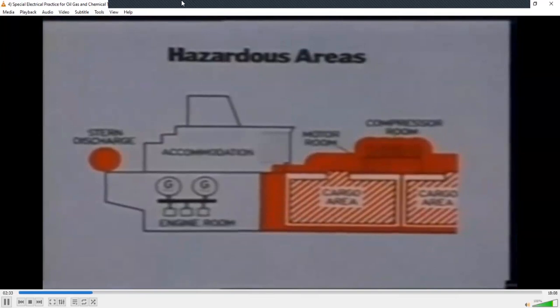The red shaded areas on this drawing show the hazardous areas relating to the electrical code of practice, which is the subject of this programme. Generally they are cofferdams next to cargo tanks, compressor rooms and pump rooms, and about a 3-metre periphery surrounding all outlets for the flammable cargo.